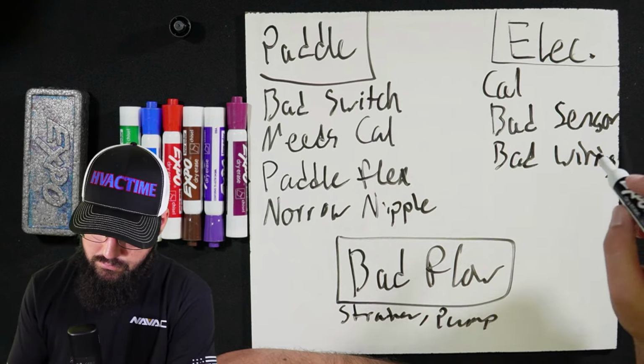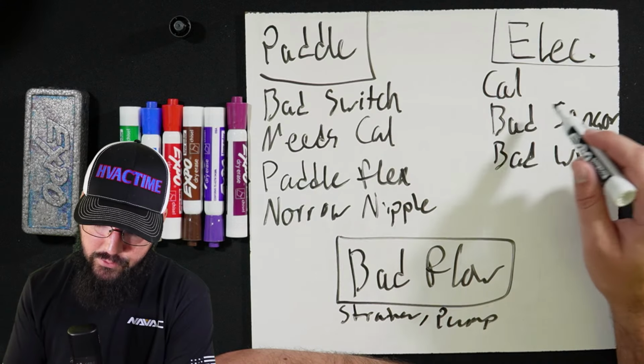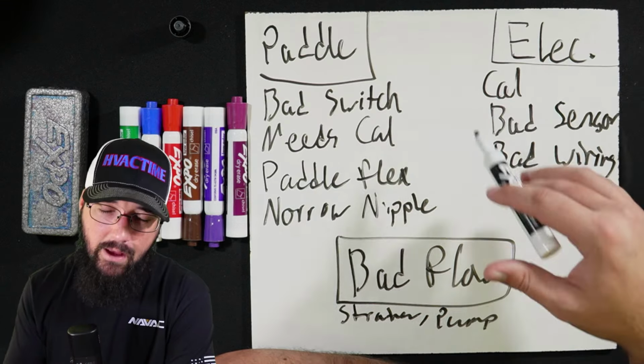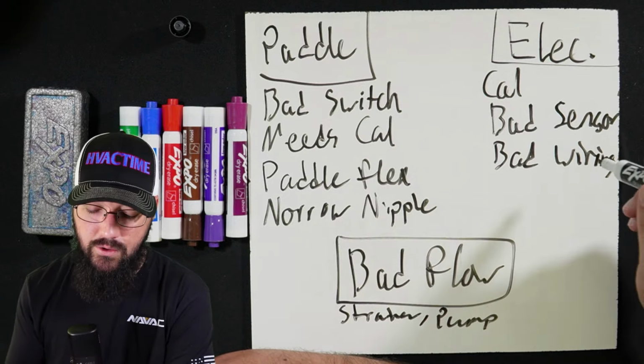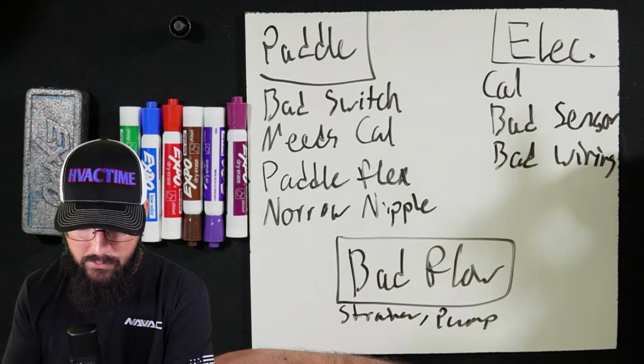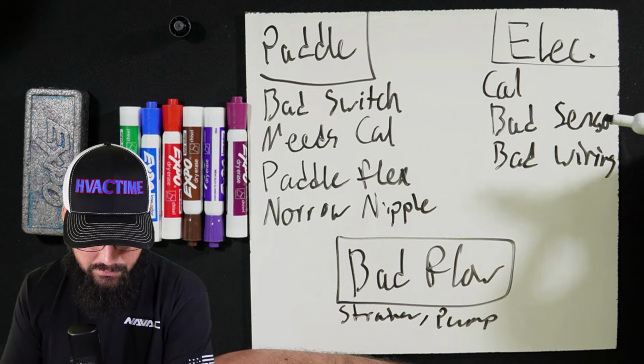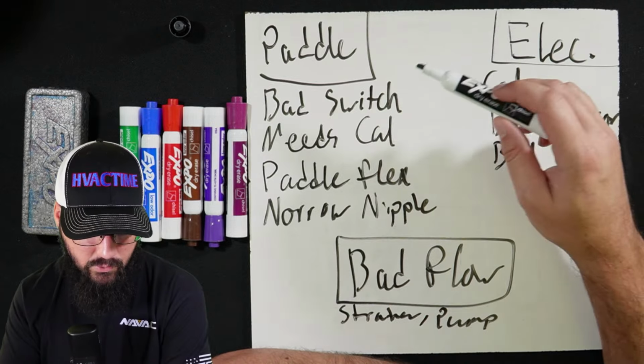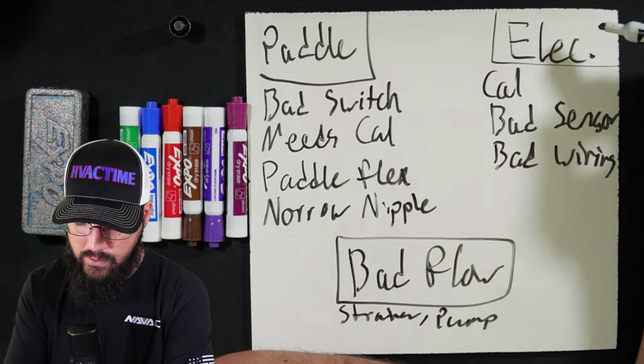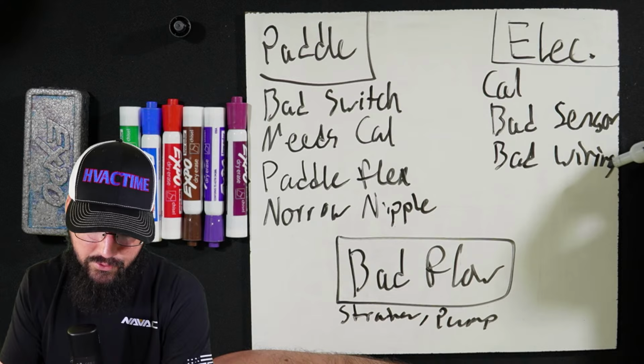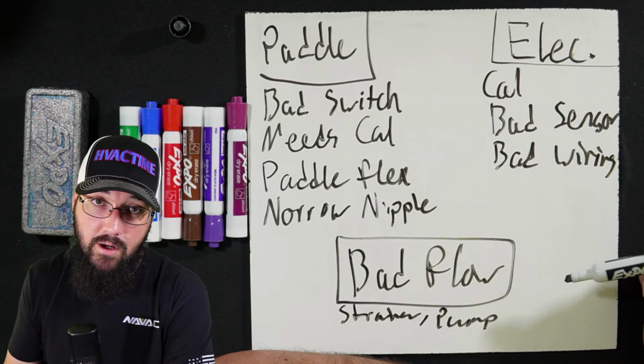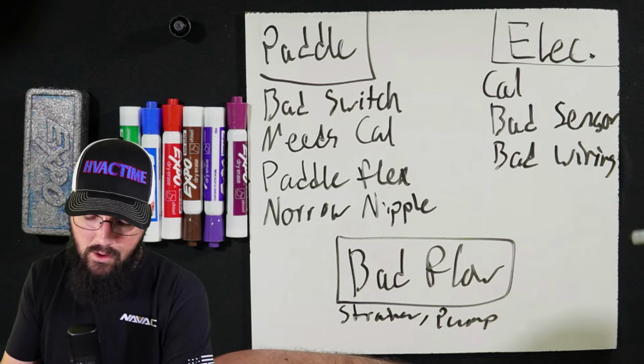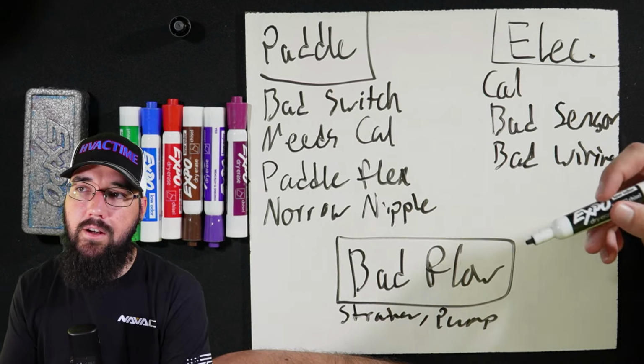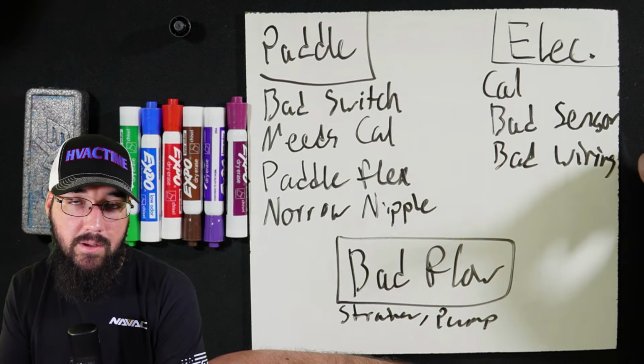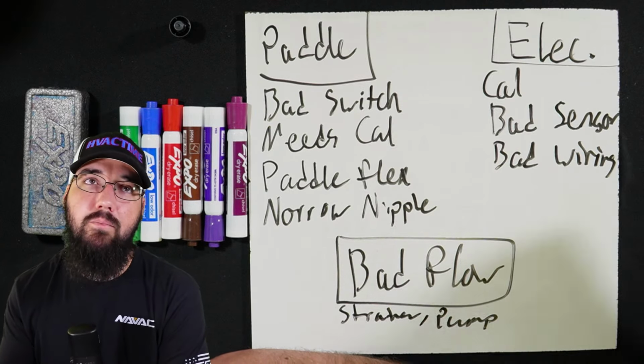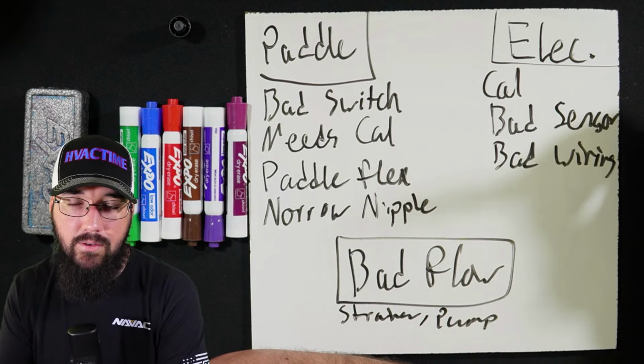And so, that goes back to, if you have a DP sensor for a flow switch or a flow sensor, that's what I would be trying to pay attention to. I think those are the main things I'm trying to watch for. Primary issues on the paddle switch. The main stuff I'm going to be checking for an electronic. It could just be a genuine flow problem. Or if we have a DP sensor, then I'm looking at, okay, what is the actual set point for my DP on this flow sensor? Is that even correct? It may not be.